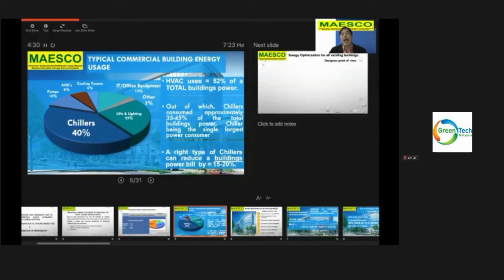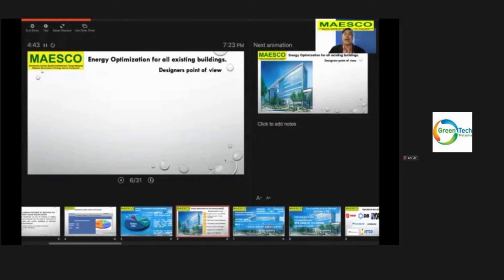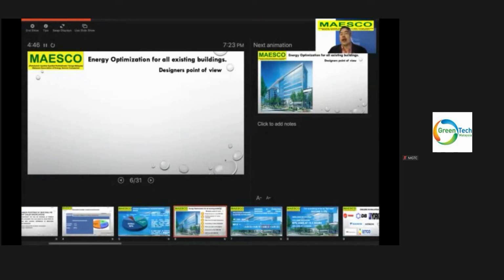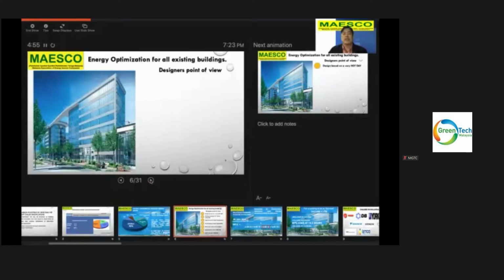And when you select the right type of chiller, it can reduce your building power bill by 15 to 20%, which will then reduce your carbon consumption. Now let's look at why energy optimization is possible, especially for all existing buildings. Let's look at the designer's point of view. When we design a building, we always base it on a very hot day, and the building material U value is estimated.